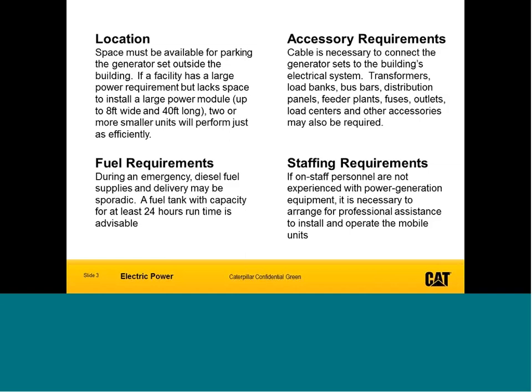Often in the heat of the moment, someone will come in and say, we need a generator, it needs to be a 20 kW, they'll hook it to the back of their truck, get it to their facility, and hit start, but the lights don't come on. They didn't get cables, or didn't get the right cables, or didn't get distribution equipment, which is basically the industrial equivalent of a large power strip for plugging in computers, tools, or other equipment. So you really need to think about the whole application as a system, and how you're going to integrate it into your building and what you're actually planning to supply.